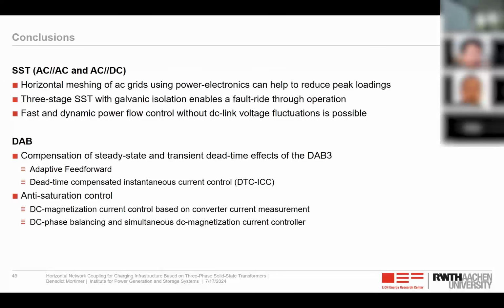For the solid-state transformer, we saw that the horizontal meshing of AC grids using power electronics can actually help to reduce the peak loading. And this is also possible without changing the protection system of the current AC grids, because we do not have an impact on the short circuit power of these AC grids. So we can leave them as they are.